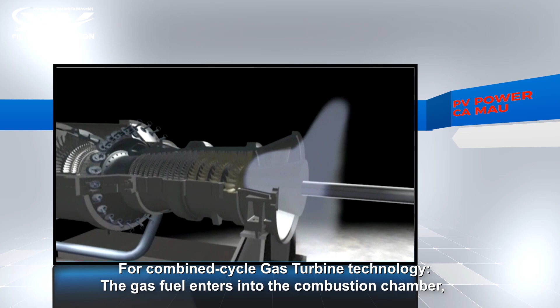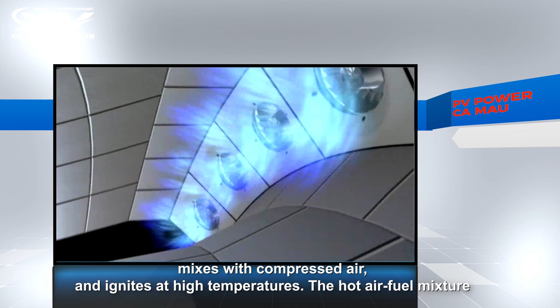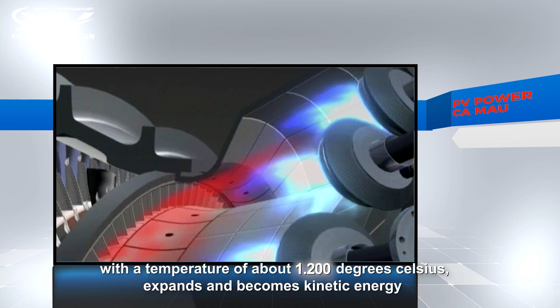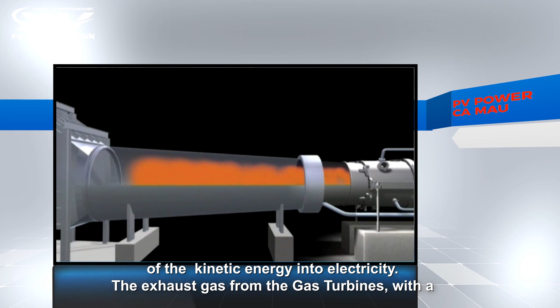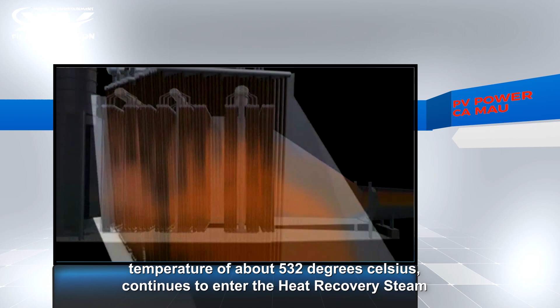For combined cycle gas turbine technology, the gas fuel enters into the combustion chamber, mixes with compressed air, and ignites at high temperatures. The hot air-fuel mixture, with a temperature of about 1200 degrees Celsius, expands and becomes kinetic energy inside the gas turbine. The kinetic energy then drives a generator that converts a portion of the kinetic energy into electricity. The exhaust gas from the gas turbines, with a temperature of about 532 degrees Celsius, continues to enter the heat recovery steam generator through 3 levels of pressure for heating water and steam generation.